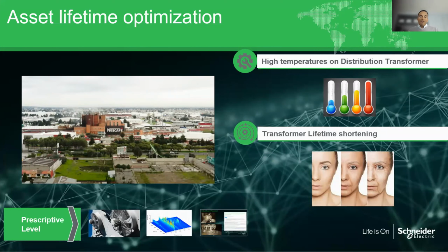So at first, we told the customer: these conditions on the transformer externally—ambient temperature, ambient humidity—plus sensors continuously detecting hotspots, with continuous thermal monitoring installed on these transformers, are suggesting elevated temperatures there.